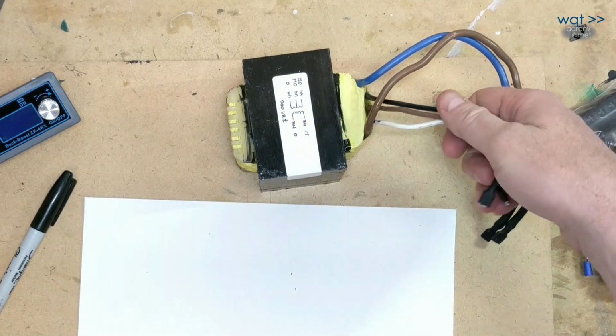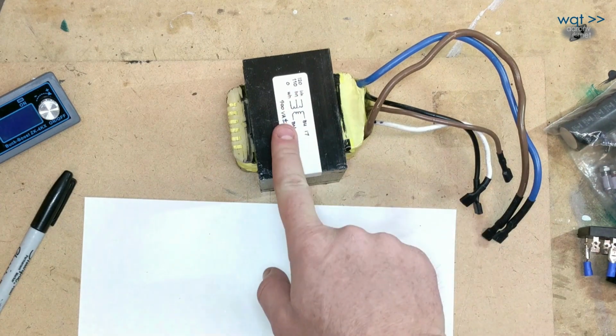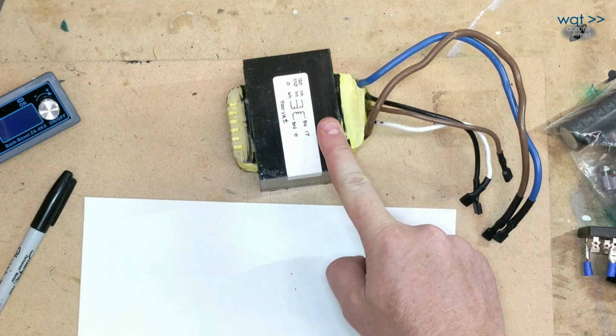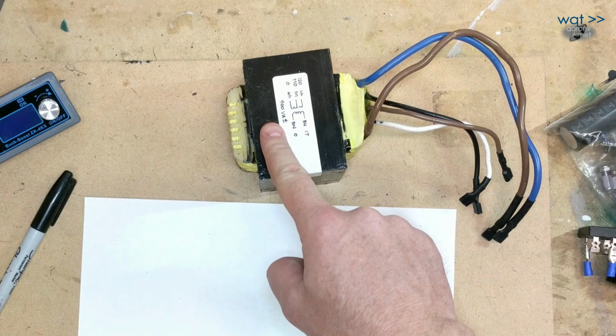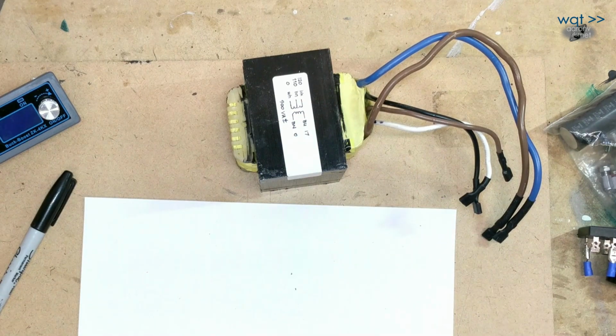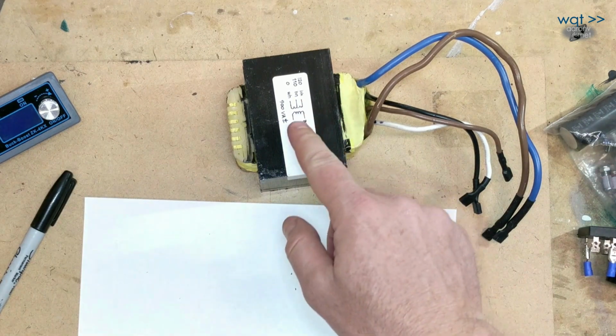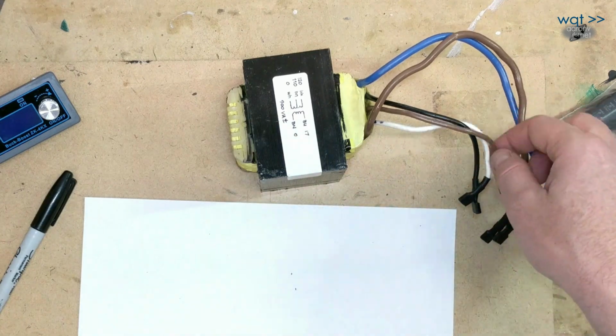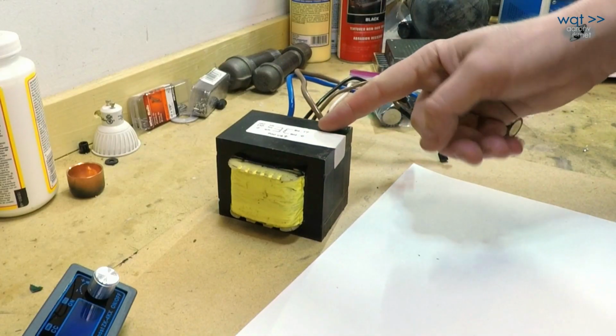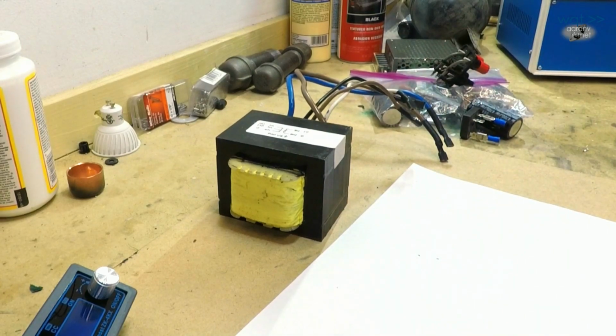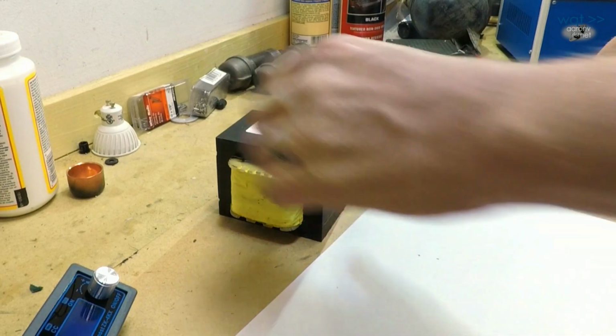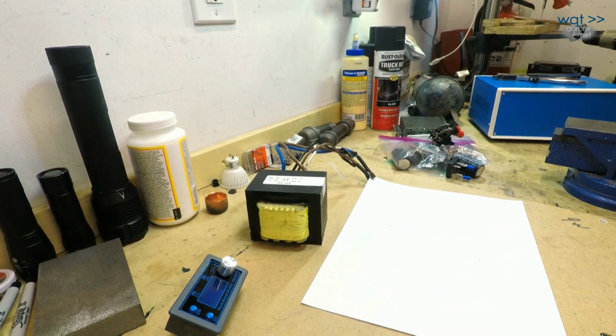What this one does for us: here on black, white, brown, we have our input. Depending on where we want to tap it, we can go 120 volt 0 on black and white, or if mains voltage is running a little low, tap it on 110 0 from brown, white. Blue and brown give us 0 and roughly 17, maybe 18 volts. And you might say, hold on a minute, I thought you were going for 24 volts DC — well, in fact we are, because this is an AC output and we need to rectify it.